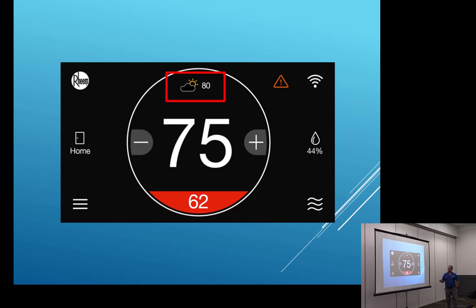Then he finally went out to the job site and happened to notice up here where the temperature display was, there was a question mark. That's for the outdoor temperature. It gets it from the outdoor unit. So he went out there, took the door off, and where the outdoor ambient temperature plugs into the board, it was plugged in, but one of the pins was not pushed in all the way on that little Molex plug. It didn't know what the temperature was. But it didn't throw an alarm either. So once they fixed that and pushed it in, the system came on and ran.